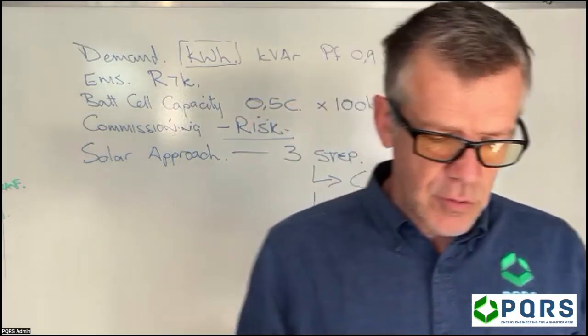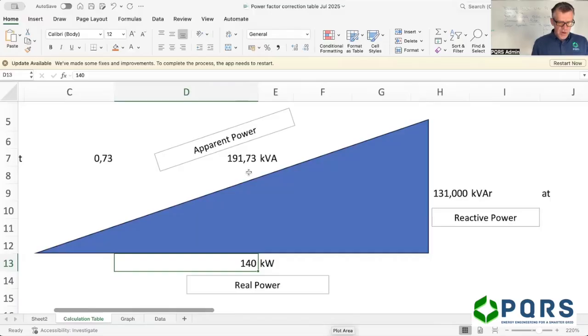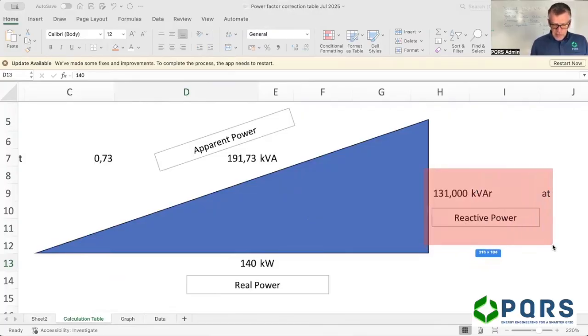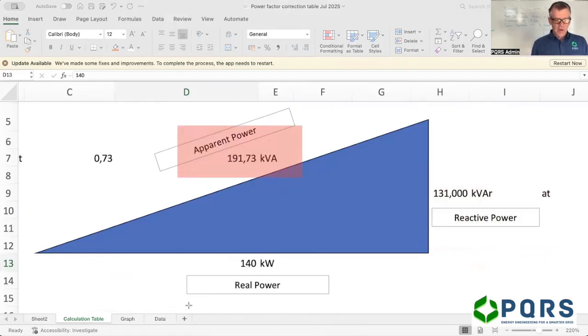Let's quickly look at your demand. What I've got on the screen is a triangle. Now these things relate to one another, where you've got real power. That's the kilowatts that you are busy drawing. And then you've got the reactive power, and the result of the reactive power gives you your kVA. It works on the Pythagorean equation. So the kVA over there is equal to the square root of the sum of the square of the kilowatts and the square of the kVAR.